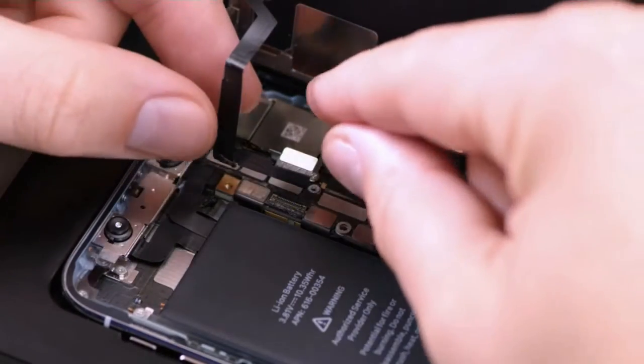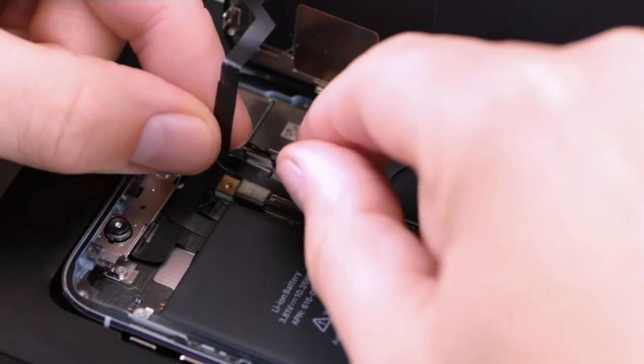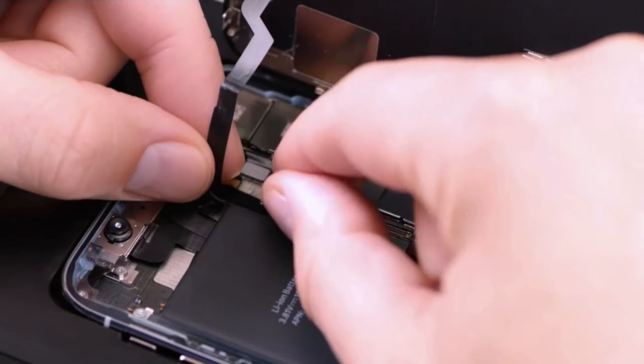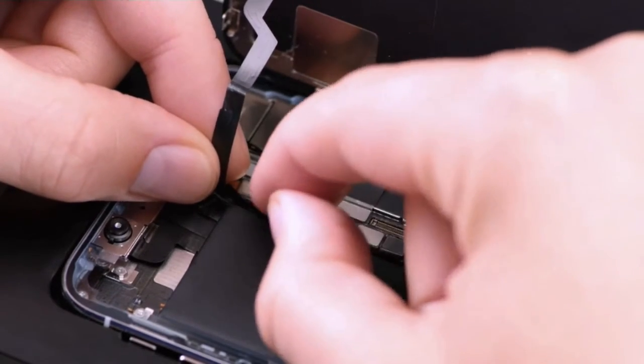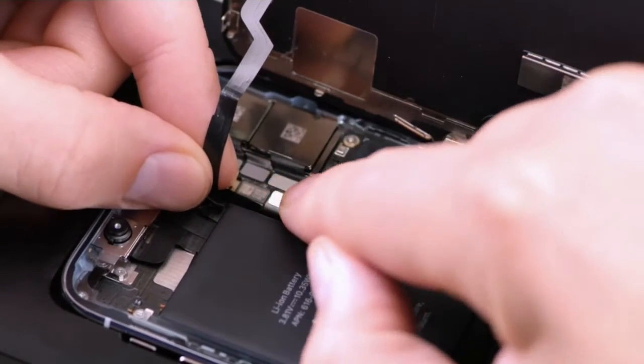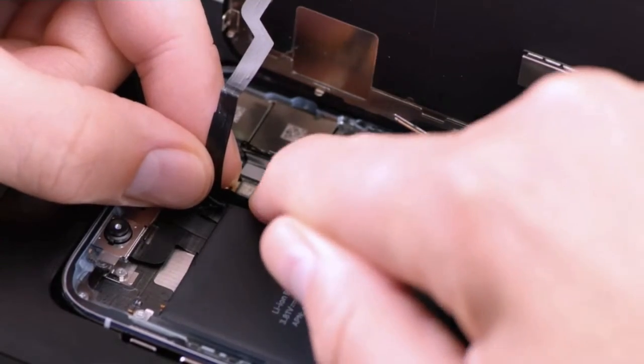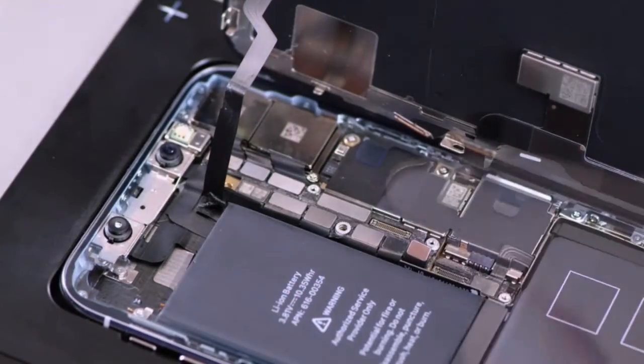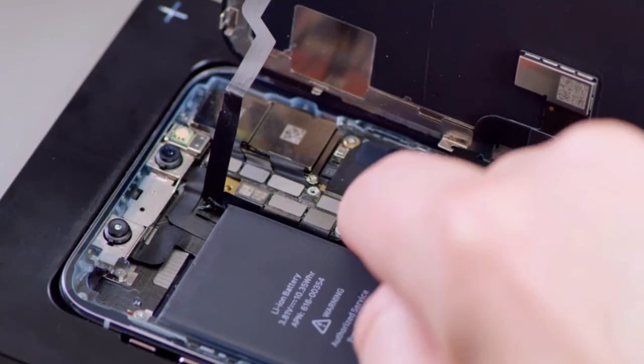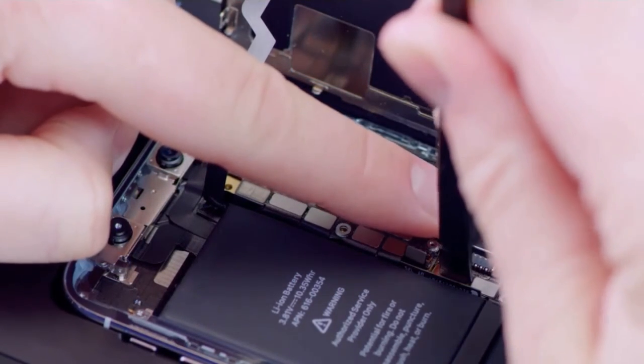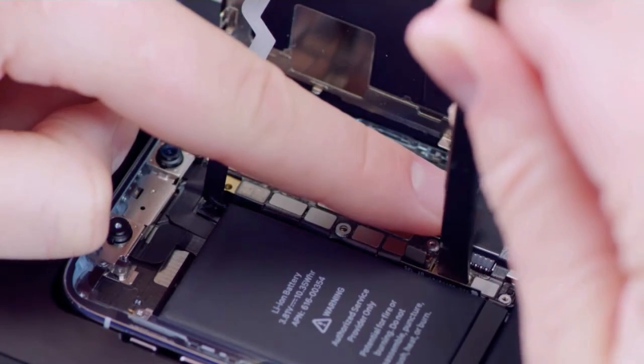Seat the upper display flex into the channel between the logic board and the battery. Connect the upper display flex. Press down gently, applying even pressure along the entire length of the connector to ensure proper seating. Connect the stack lower flex connectors. Press down gently, applying even pressure along the entire length of each connector.